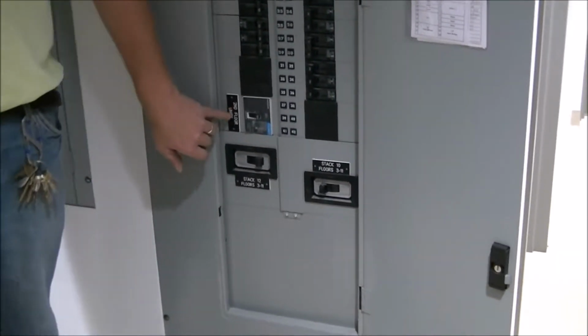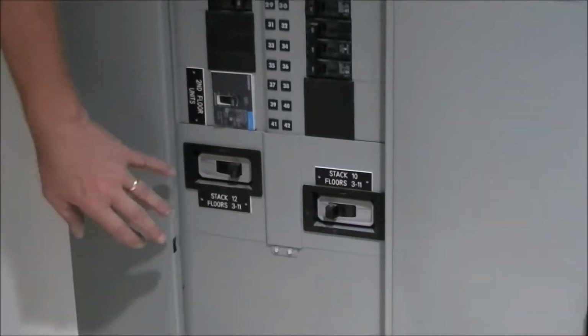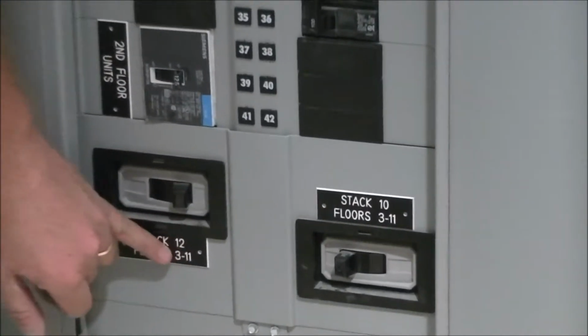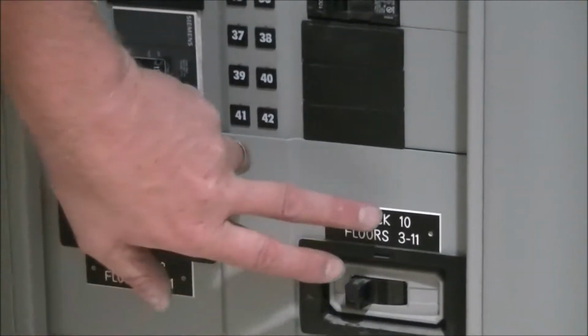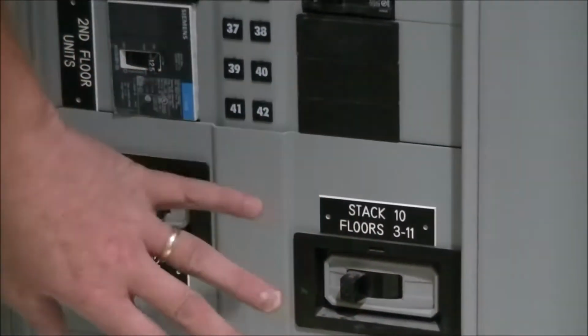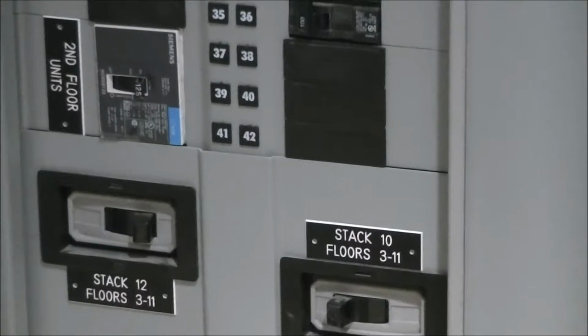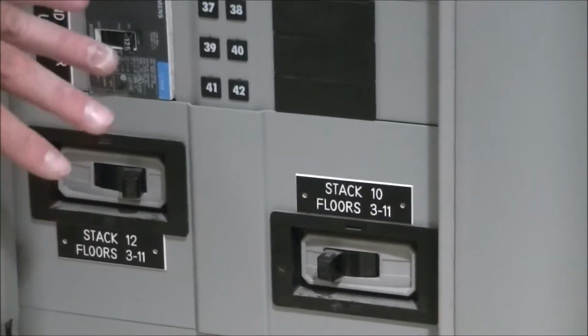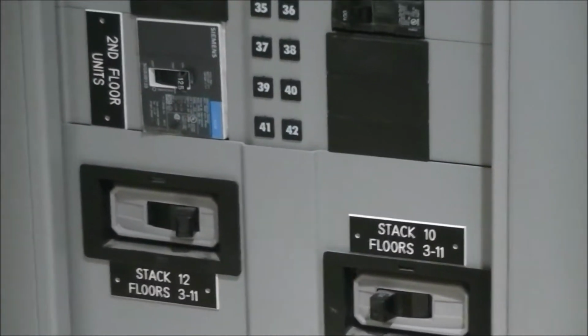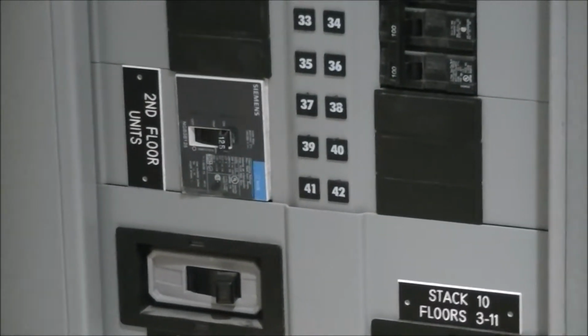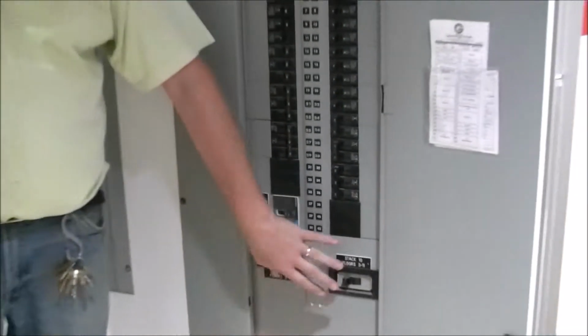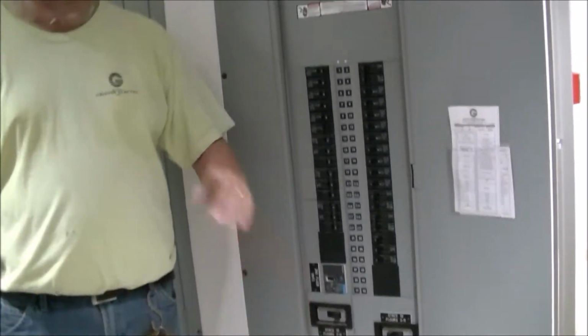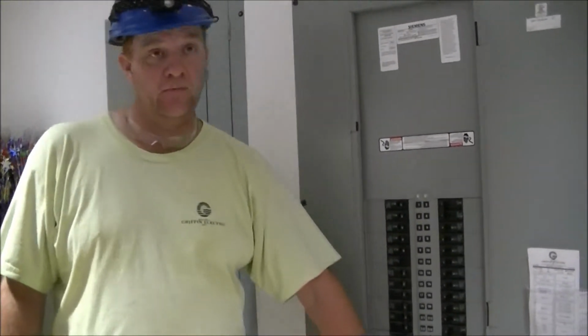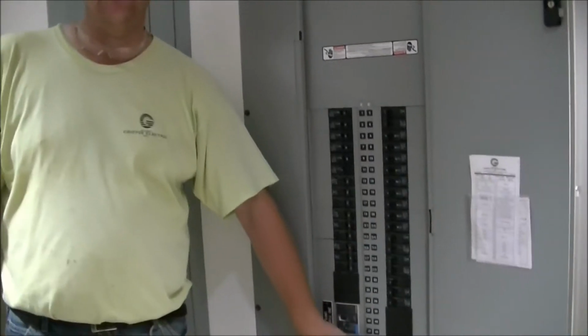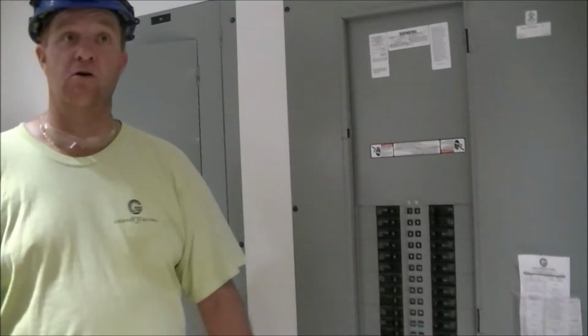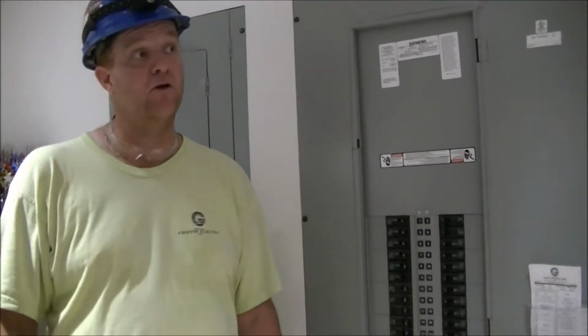The second floor units are fed out of this panel. Stack 12, floors 3 to 11, and stack 10, floors 3 to 11, are out of this panel, so they're the only units fed from here. Everything else is fed from the second floor and goes up from there. So if you've lost power and can't find it on the second floor in your tenant units, you're going to find it down here. It's something to keep in mind if you're running all over the building wondering why the power's gone out.